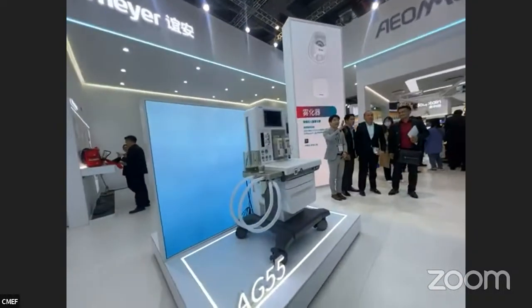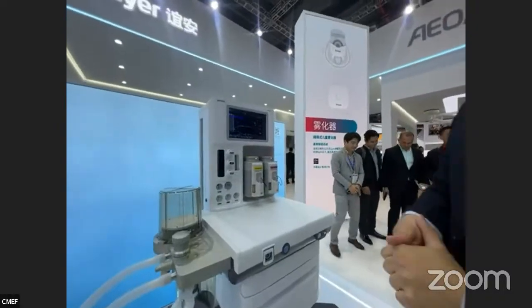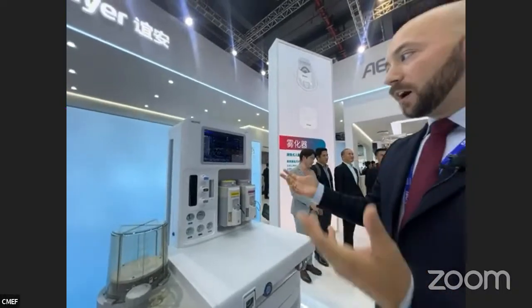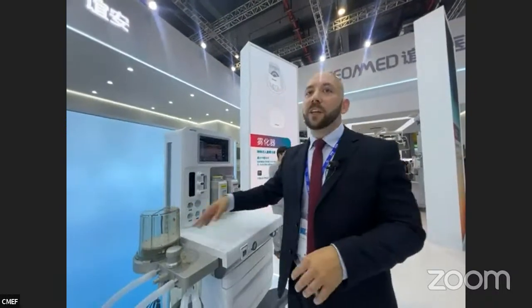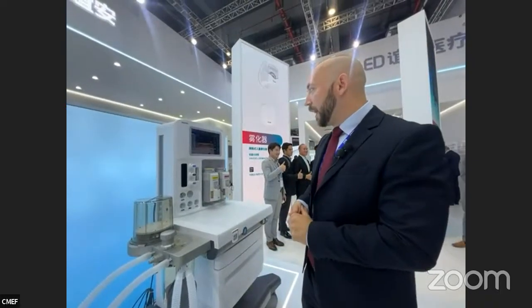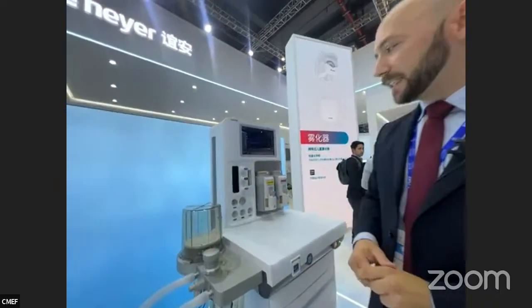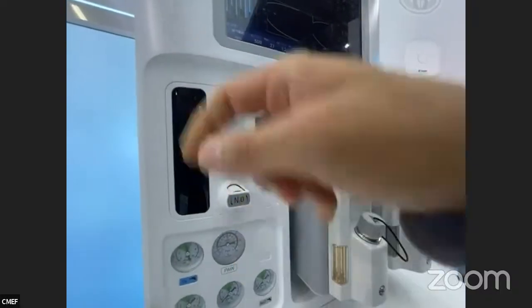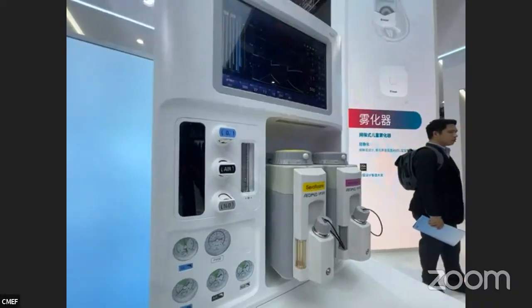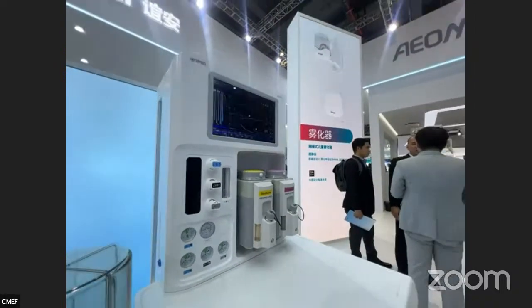This model is called AG55, and it presents a slightly simplified version of the AG70. What are the main differences? The first difference is that this system is not utilizing volume reflector technology. We are utilizing bellows, which in some cases can still be preferred by certain medical staff based on their habits in usage. In addition, the flow meter in this device is a mechanical flow meter with electronic measurement, so we combine the best things from electronic and mechanical flow meters.